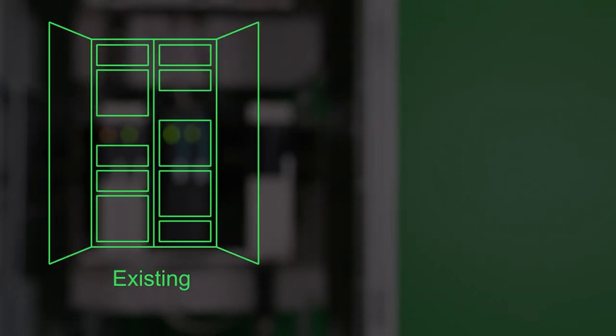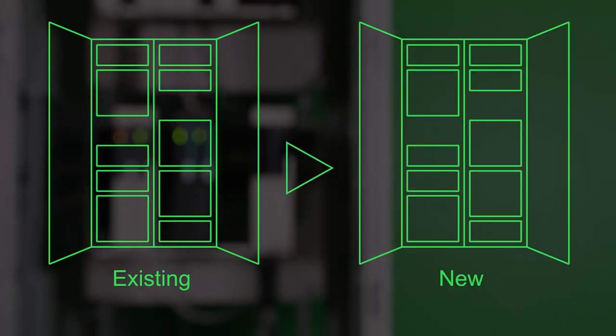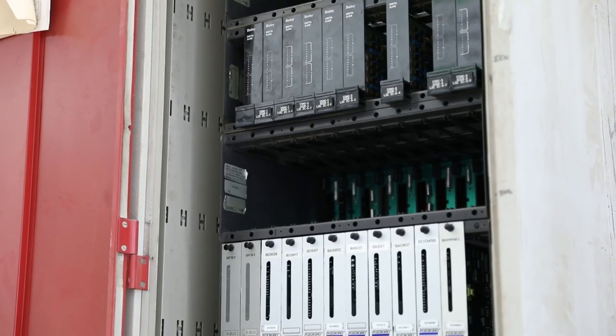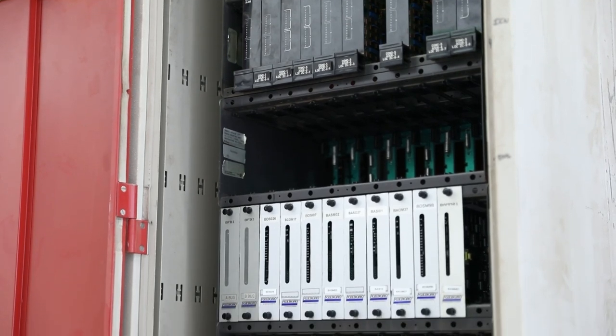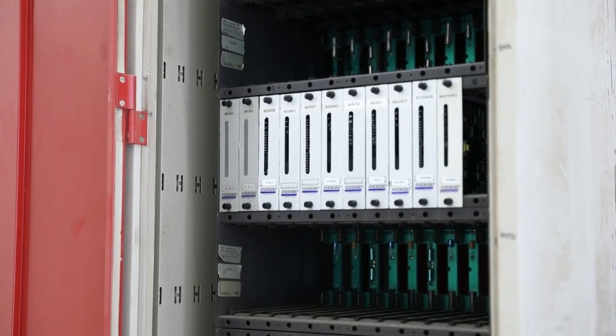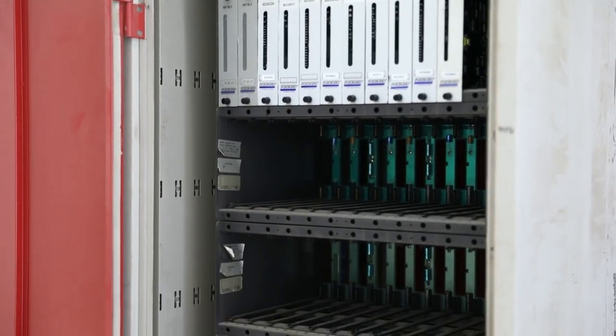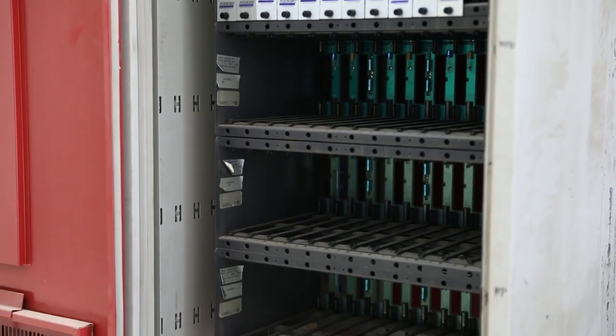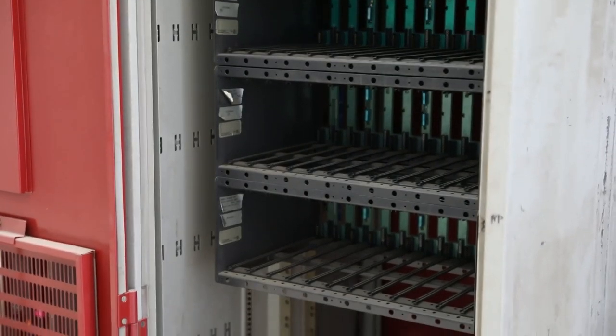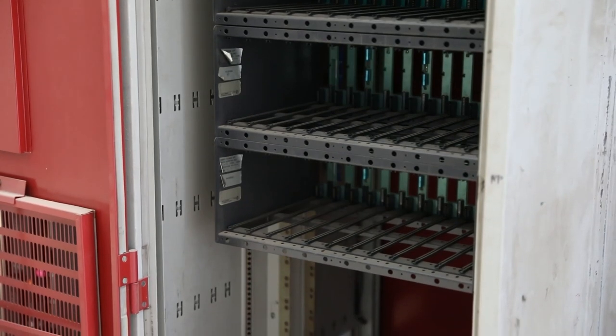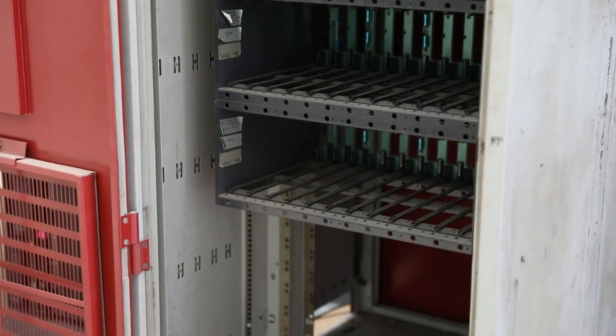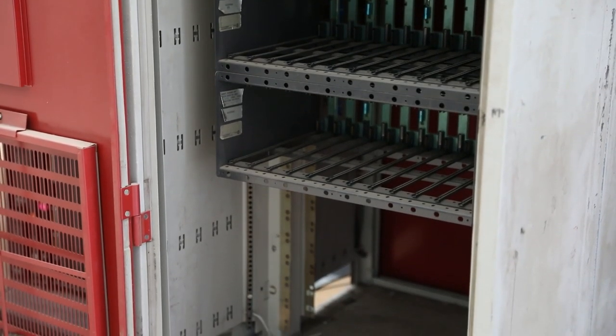While many companies want the advantage of mounting new controllers in the same cabinet as the old ones, some choose to make use of an external cabinet. A number of elements are retained and can stay just as they are. We don't touch certain critical connections, including those from the field device to the instrument junction box, or from there to the marshaling area, or from that spot to the field termination assembly, or from there to the rack.